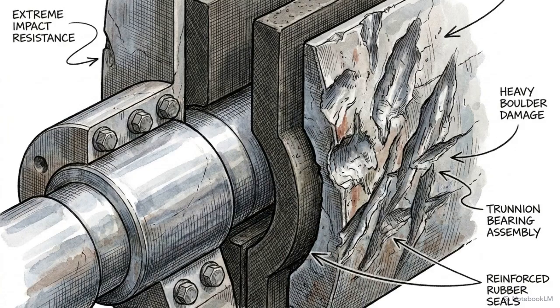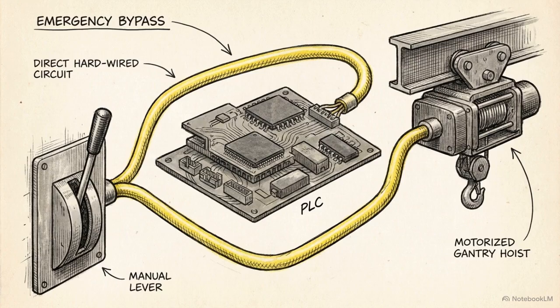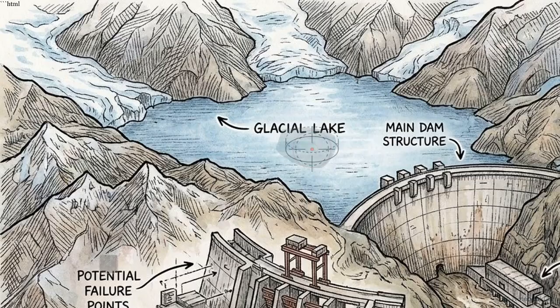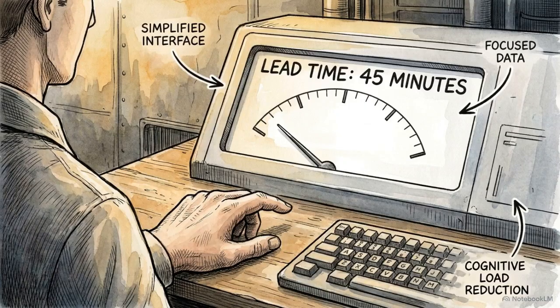On the hardware side, this requires upgrading gate seals, trunnion bearings, and guide systems to explicitly tolerate high debris loads and boulder impacts. To protect the control logic, designers must install physically independent, hardwired emergency actuating circuits for every individual gate, completely bypassing central automation networks. To mitigate human error, advanced sensor fusion can integrate live upstream glaciological and hydrometric data directly into the dam's SCADA system. This early warning integration directly addresses the human reliability analysis matrix by lengthening the decision window and reducing cognitive overload under pressure.